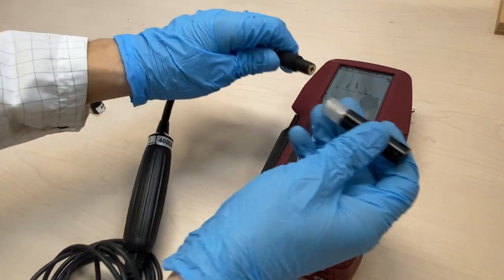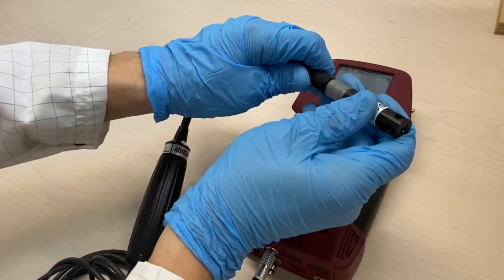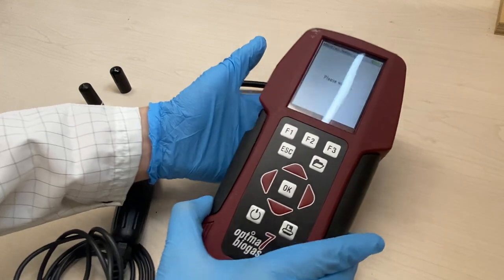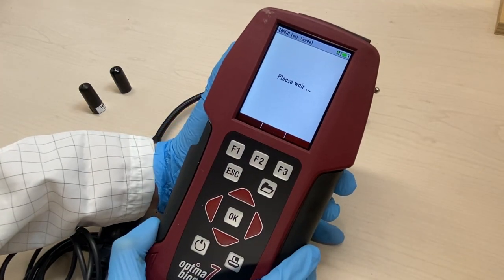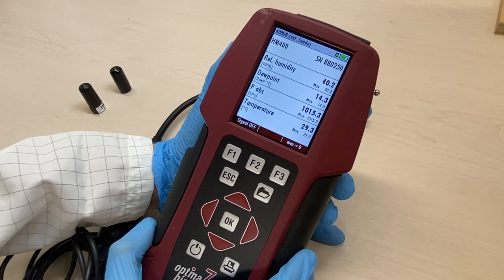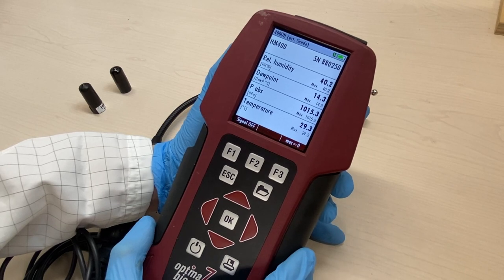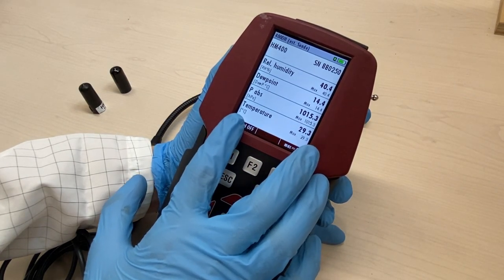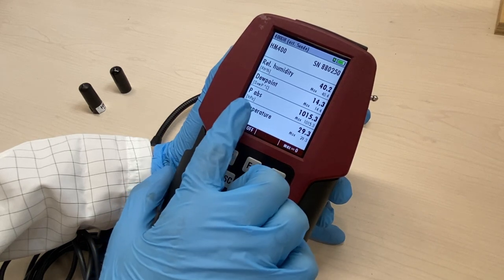Attach the jack end of the sensor onto the probe. It will take a few seconds for the instrument to detect the connection of the sensor. Dew point and temperature will default to Celsius. The absolute pressure reading will default to hectopascals.